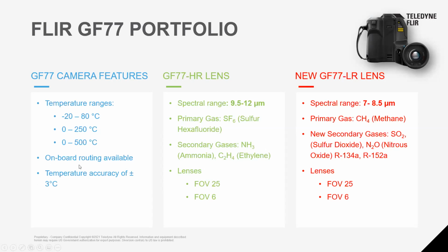We also have something called routing. It's part of our software package that is enabled on the camera. If you have many different assets that you need to inspect, you can pre-populate a route in your camera. So it'll say, okay, first we go to asset 1, and then asset 2, asset 3. For each asset, you take an image or a video, and you can take notes on it. It helps make sure that you complete everything you set out to do without wasting time or energy, missing things or having to double back. The accuracy on the thermal imaging camera is plus or minus 3 degrees Celsius, which is pretty good for predictive preventative maintenance, where you're really just looking for heat anomalies.